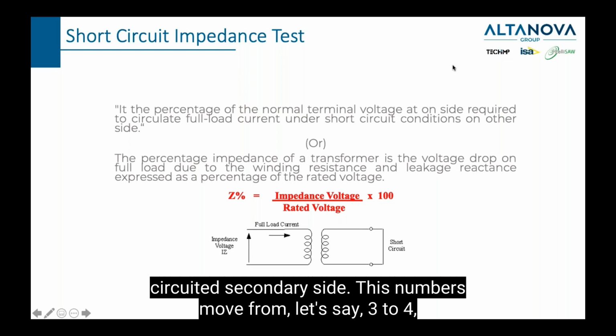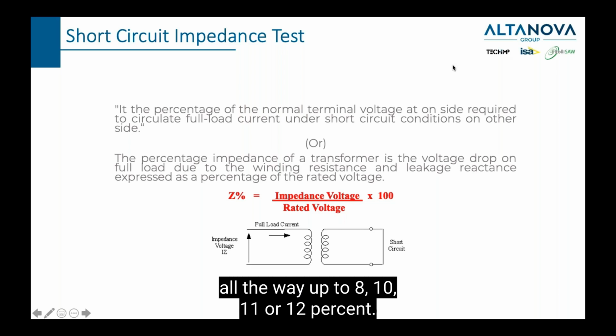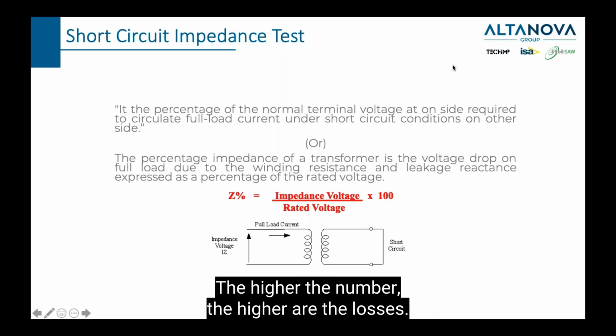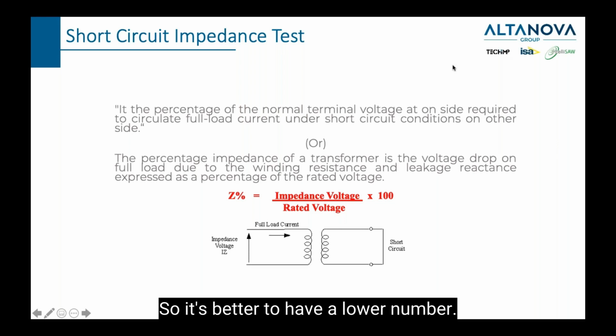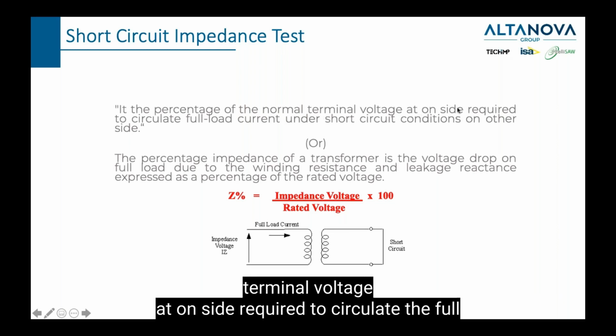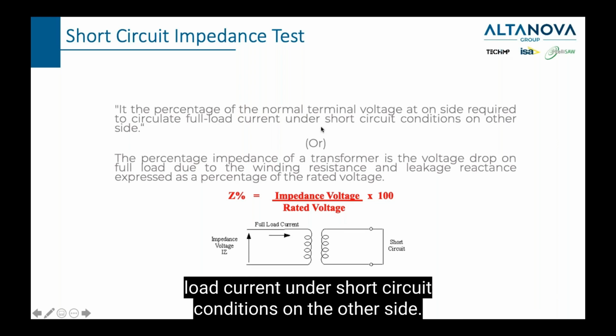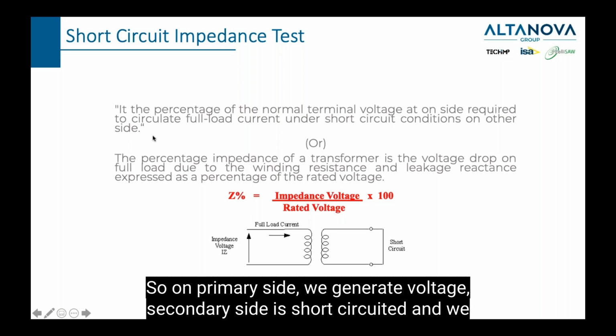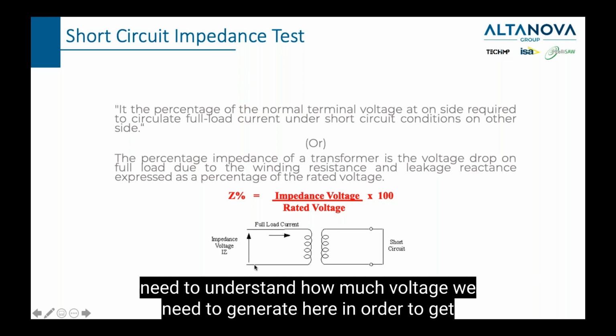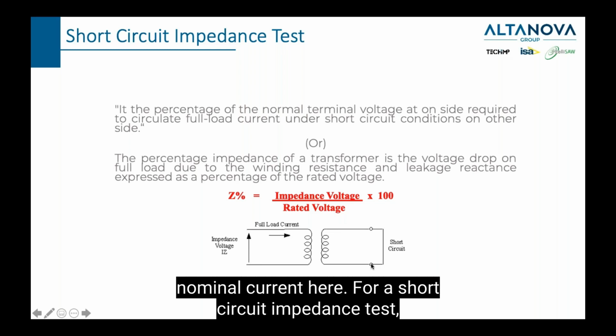These numbers move from, let's say, 3 to 4 all the way up to 8, 10, 11, or 12%. The higher the number, the higher the losses, so it's better to have a lower number. But let us read what is written here. It is the percentage of the normal terminal voltage on one side required to circulate a full load current under short circuit conditions on the other side. So on the primary side, we generate voltage, the secondary side is short circuited, and we need to understand how much voltage we need to generate here in order to get nominal current here.